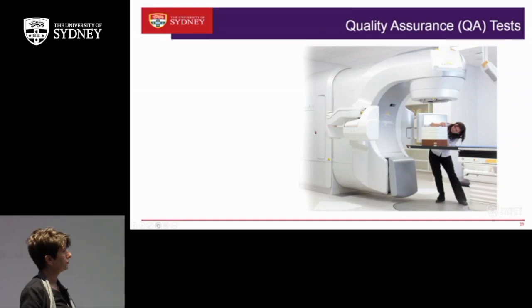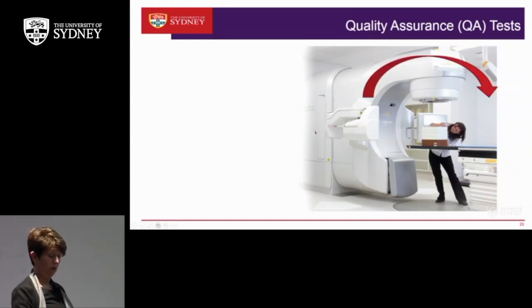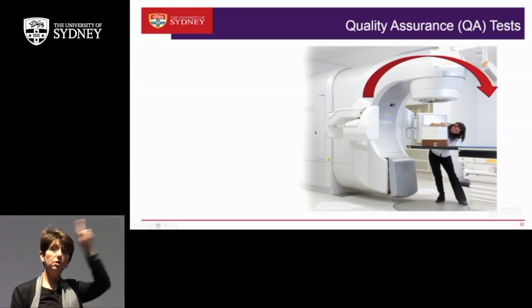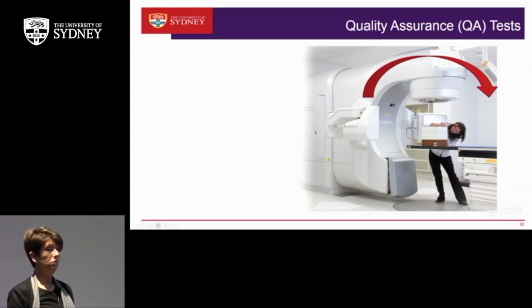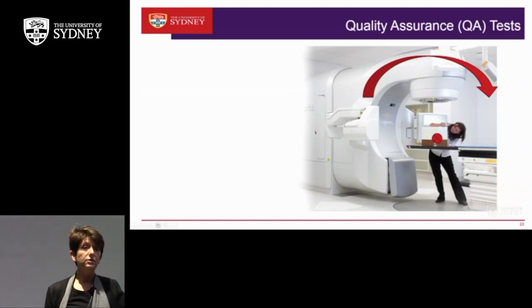of radiation. Now, the thing to understand is that these machines, this is the gantry here, the linac, rotates around a point in space. Even though it weighs several tonnes, it actually rotates about a point in space, which we call the isocenter. Now, this point in space is about the size of a pea. In actual fact, it's even smaller than a pea.